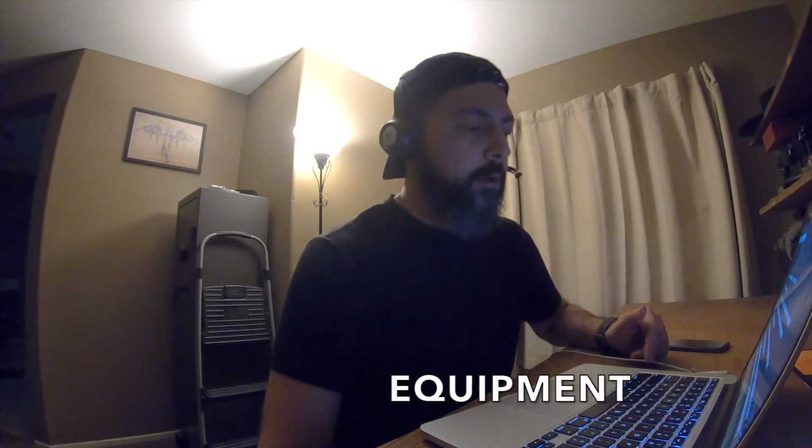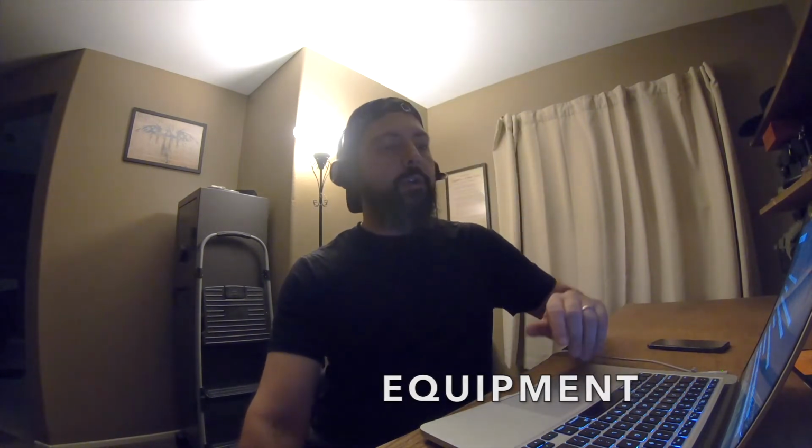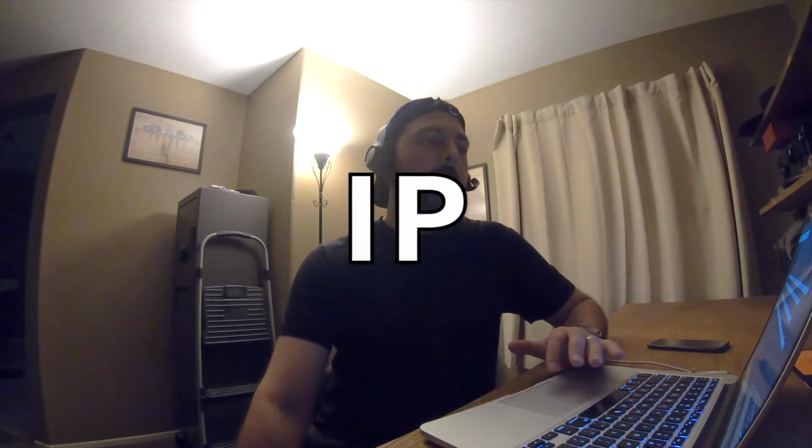Also, we discussed earlier the equipment. So the centrifuge, the EKG, the height and weight scale, the blood pressure cuffs, the -20 or -70 freezer, access to dry ice. How often are they calibrated? Do we have calibration logs? Who's calibrating it? What's the vendor? Also, the temperature logs as well. And that's going to be for the IP, which is the next slide.